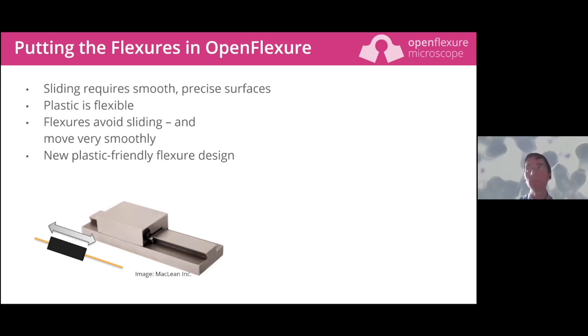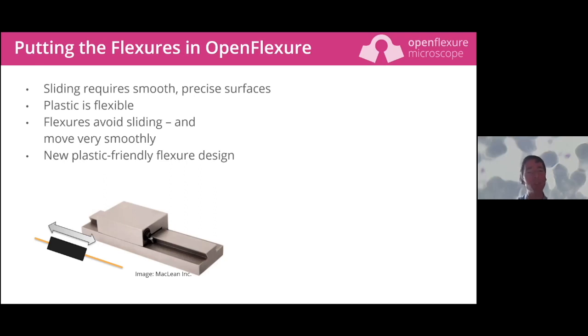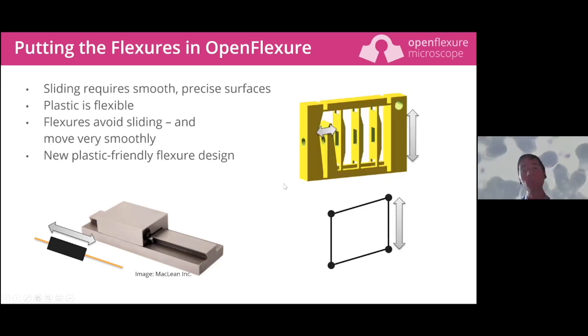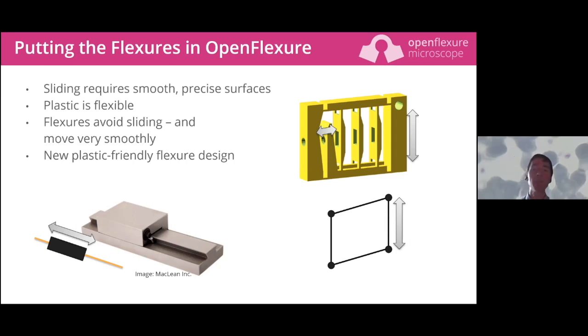This is all relatively expensive to engineer out of metal, and it doesn't scale to mass production as well as you'd like. So could we just 3D print this? Yes, but if you just 3D print this design you won't have a very good translation stage - it'll be sticky, it'll wear quickly, and the tolerances are too loose. So instead, for the OpenFlexure microscope - the clue's in the name - we use flexures: thin parts in the plastic, exploiting the fact that plastic is soft and flexible so we can move it by bending it.